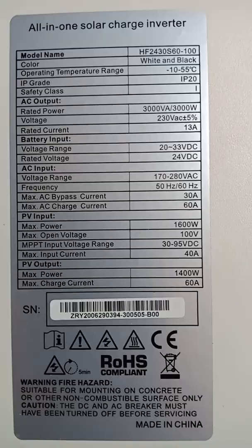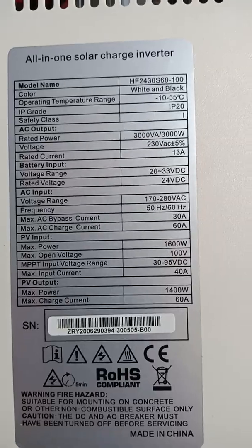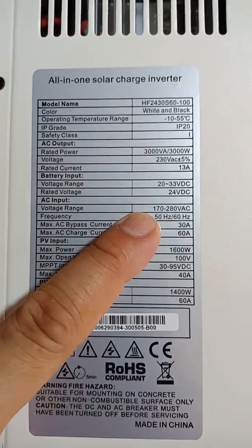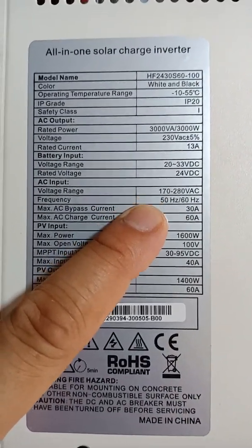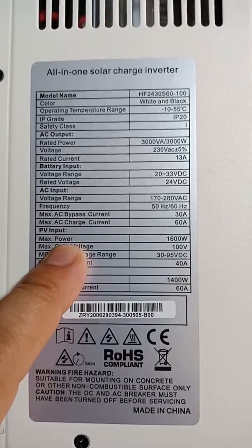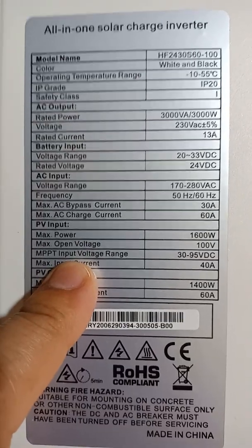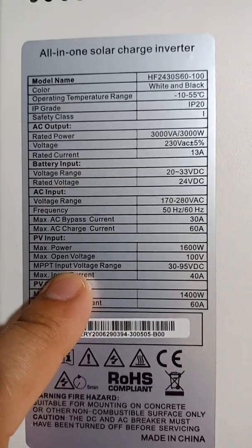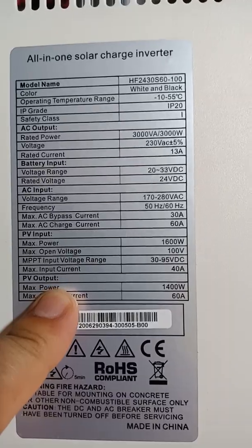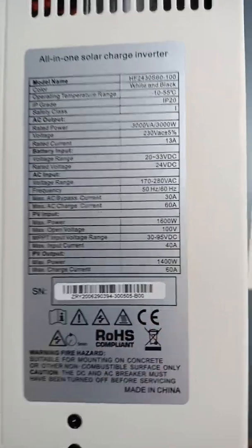It's a 3,000 watt unit. The battery voltage range is 20 to 33 volts, so it's for a 24-volt battery. AC input is 170 to 280 volts, frequency is automatic 50 to 60 Hz. Max solar power is 1,600 watts, max PV voltage is 100 volts. The MPPT input range is 30 to 95 volts DC, with a max current of 60 amps.